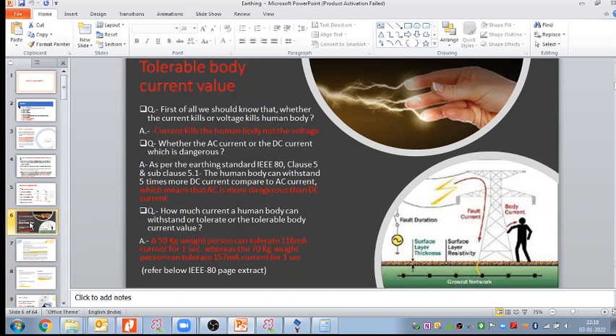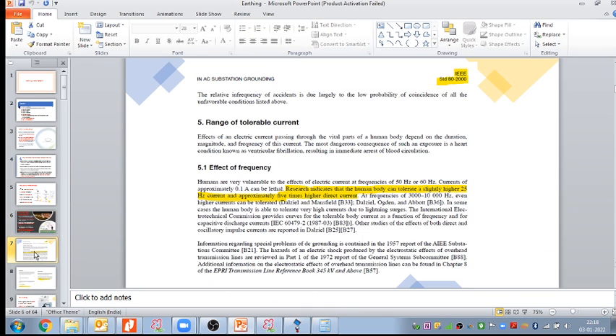We discussed here which is dangerous, AC current or DC current. As per the earthing standard IEEE 80, clause 5 and subclause 5.1, the human body can withstand 5 times more DC current compared to AC current, which means that AC is more dangerous than DC current. How much current can a 50 kg body weight and a 70 kg body weight tolerate? For 50 kg, 116 milliampere, and for 70 kg, 157 milliampere per 1 second. This is the page of the relevant IEEE standard that we have taken.